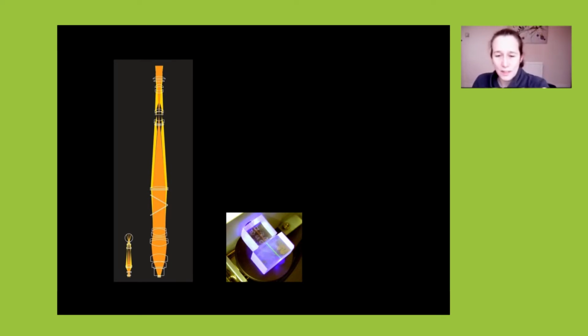So the image that's shown in the bottom here is taken from our trip to the glass factory in Wales, where we've put a UV laser pointer through 2 different supposedly BK7 tubes. You can see that one is strongly fluorescent in the kind of blue-green, one is weakly fluorescent in the orange. We can use neither of these because any fluorescence that results from excitation of the lens elements then makes its way to the image and would compromise our image contrast.